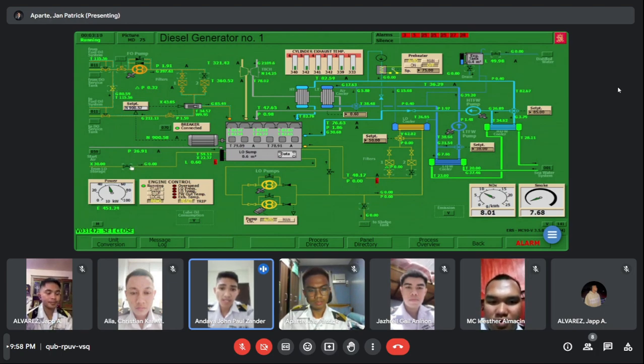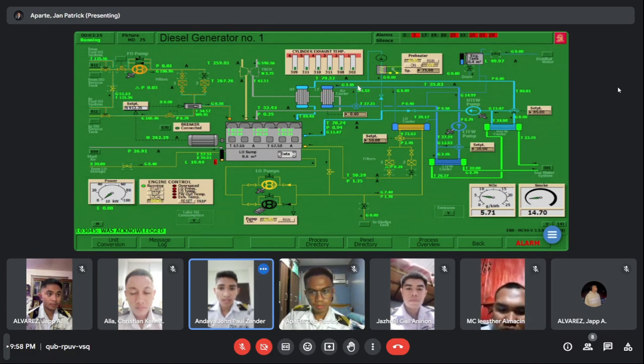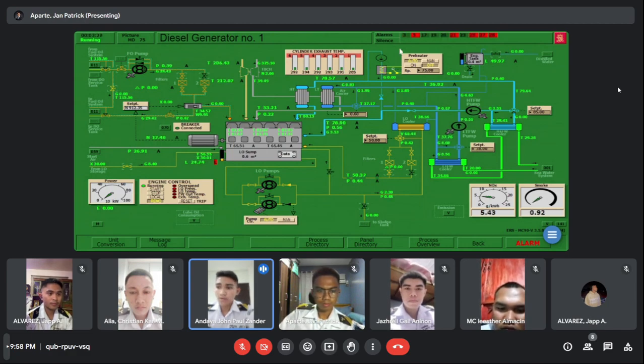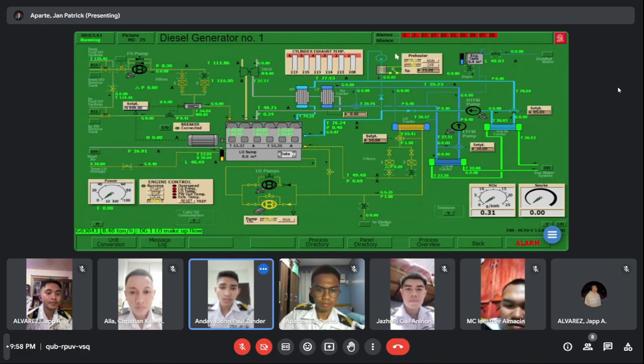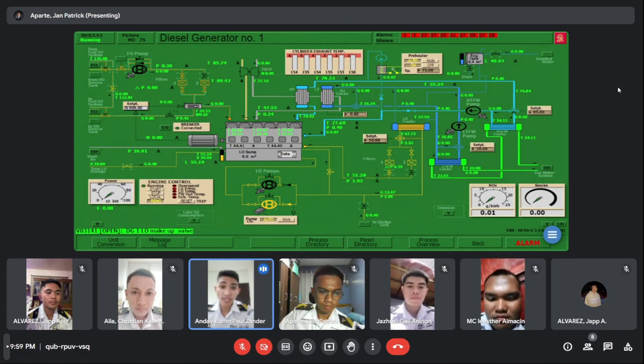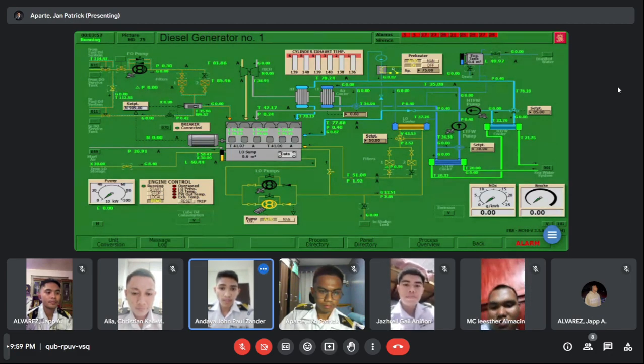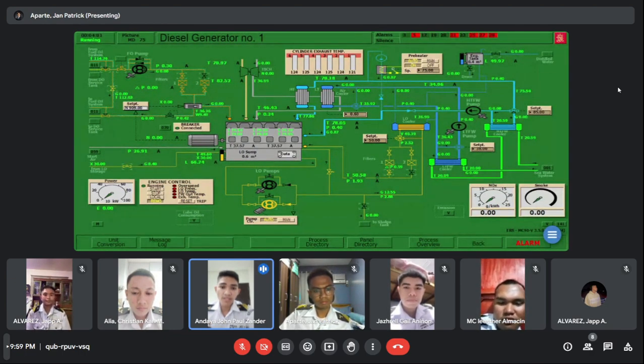Again, turn off the valve on DG number 1 because it is at low level again, since it is consuming liters. Then return the valve to open to raise the level of the lubrication oil system tank of DG number 1. While waiting, make sure to monitor the parameters so we are sure there are no alarms. DG number 1 is already in running condition, so we just monitor the level of the lubrication oil and the pressure of the fuel oil system. After reaching 70 to 80%, let's go back to diesel generator number 2.